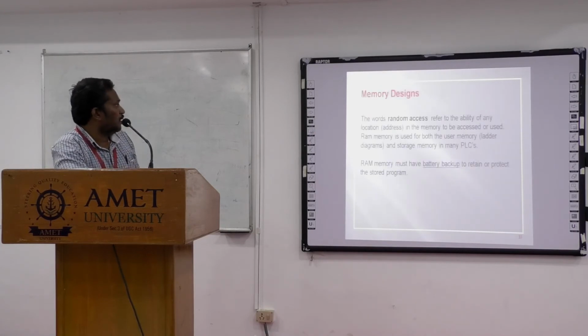The words random access refer to the ability of any location, that means address, in the memory to be accessed. RAM memory is used for both user memory and storage memory in many PLCs. RAM memory must have battery backup to retain or protect the stored program, because it is a volatile type memory.